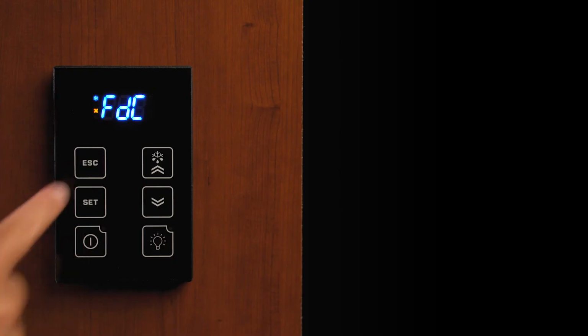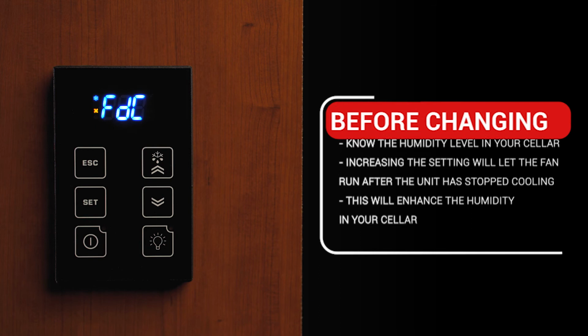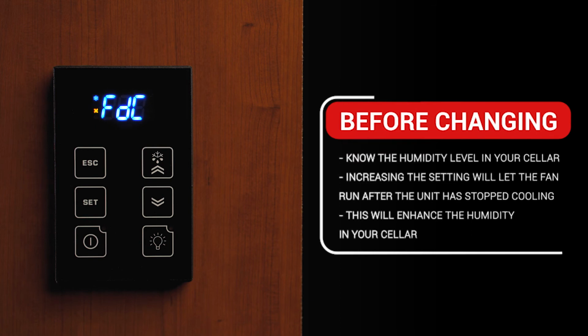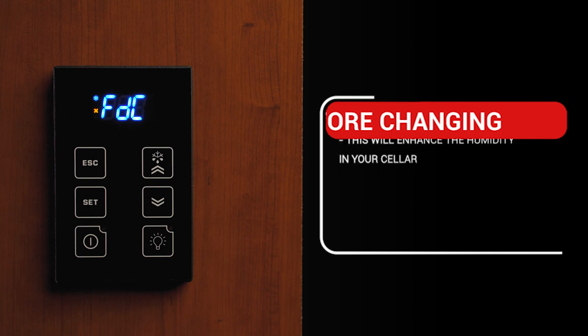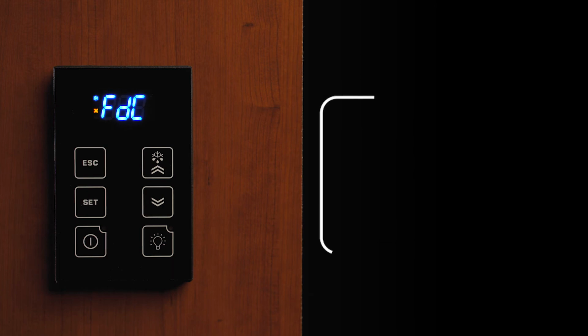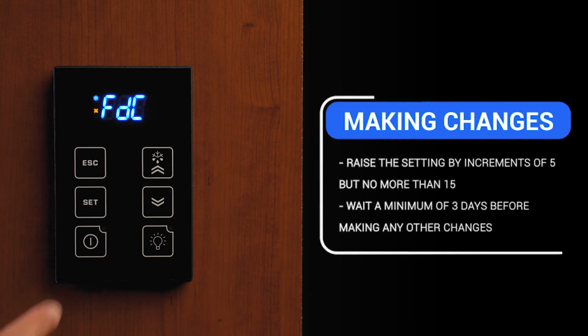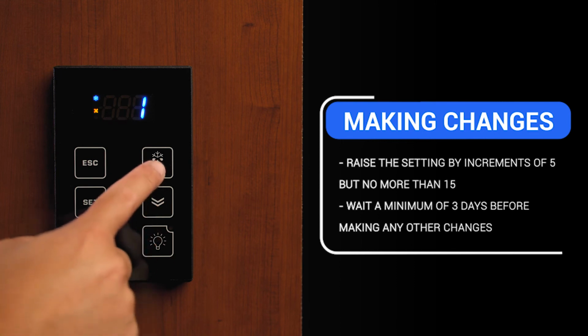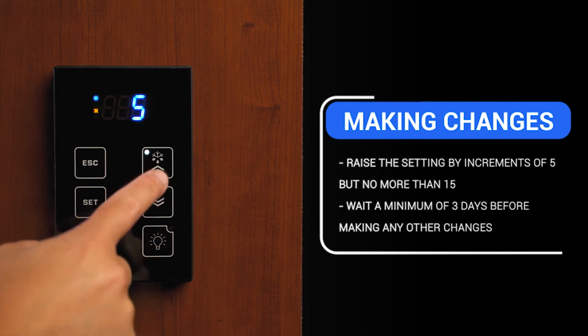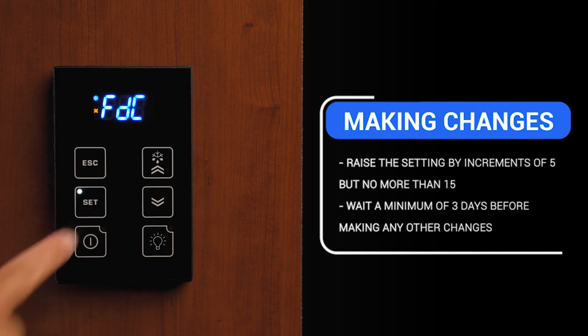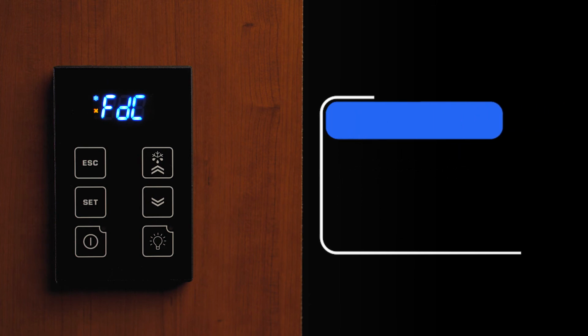Before making any changes to this parameter, it would be best to know what the humidity level is in your cellar. Increasing the setting will have the evaporator fan run after the unit has stopped cooling to allow the fan to blow some of the moisture on the coil to try to enhance the humidity in the cellar. If needed, you will want to raise the setting by increments of 5, but no more than 15 minutes, and you should wait a minimum of 3 days before making any other changes. This setting is only beneficial if there is still moisture on the coil.